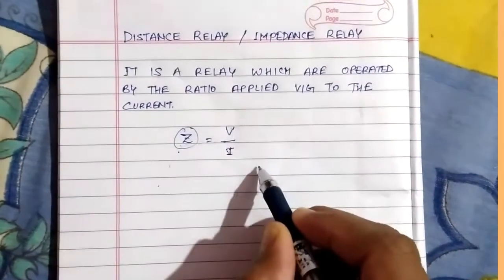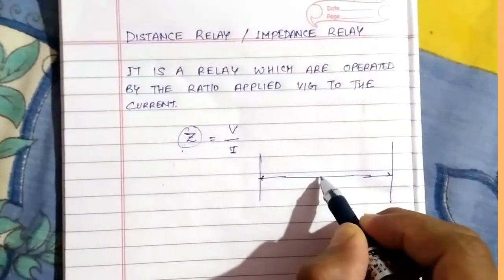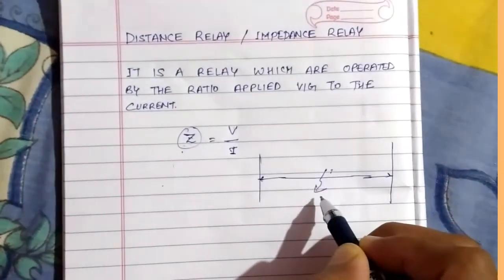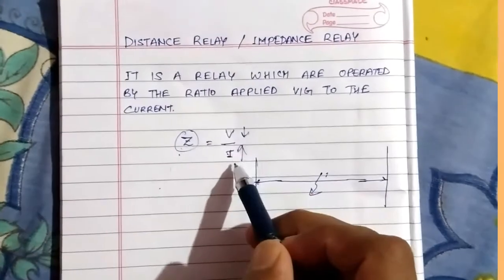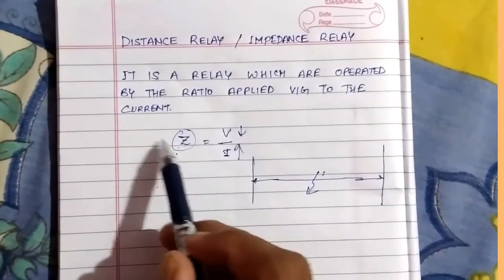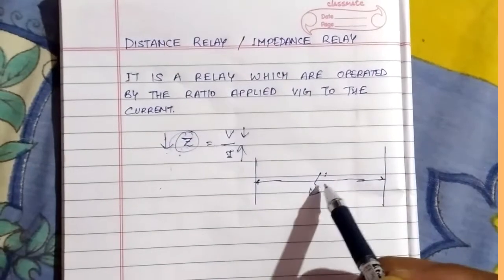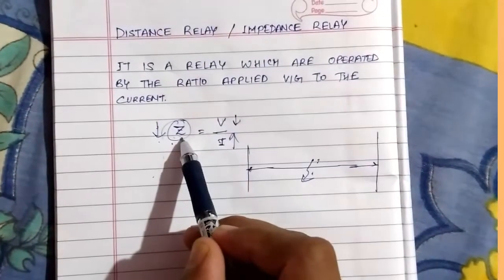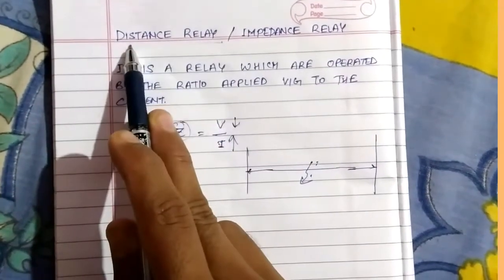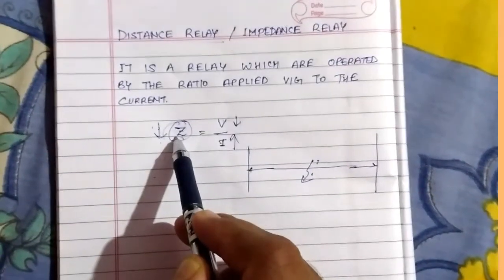In a long transmission line, if a fault occurs, the value of current is increased and the voltage is decreased, so the impedance value is also decreased. Due to this fault, the impedance is changed. If the impedance value changes, the preset value in the distance relay is also changed, and it will activate the tripping mechanism.